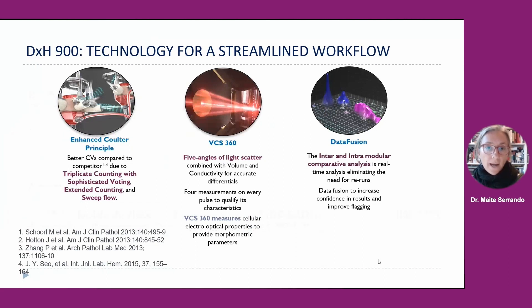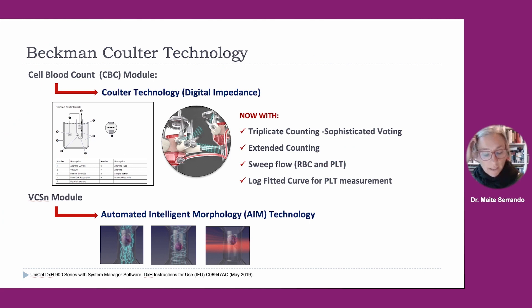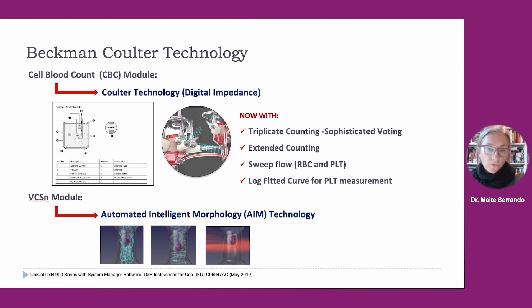Let's talk about Beckman Coulter hematology technology, which is based on two modules. The first module is the CBC module, based on the Coulter principle, that accurately counts and sizes cells by detecting and measuring changes in electrical resistance. The DXH 900 has digital impedance with triple-aperture counting and sophisticated voting, extended counting, and sweep flow in order to prevent recirculation of cells, especially red blood cells and platelets behind the aperture. The second module is the VCSn module, or automated intelligent morphology technology, that provides excellent results for leukocyte differential.